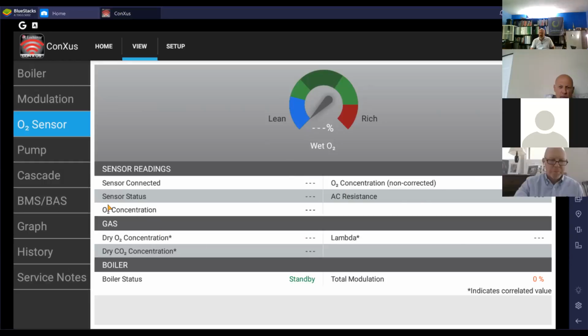You'll notice that it does not give you CO, and that's intentional, really, because CO sensors are going to need to be replaced. And we don't want to have a scenario where somebody doesn't replace the CO sensor and they're relying on that there, thinking, hey, my boiler's running okay, and it ends up not being. So that's an intentional thing.